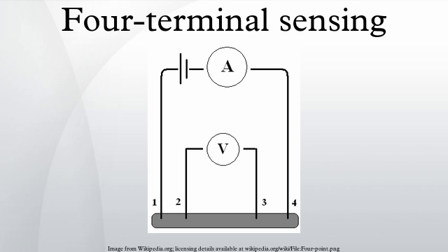A pair of sense connections are made immediately adjacent to the target impedance, so that they do not include the voltage drop in the force leads or contacts. Since almost no current flows to the measuring instrument, the voltage drop in the sense leads is negligible.